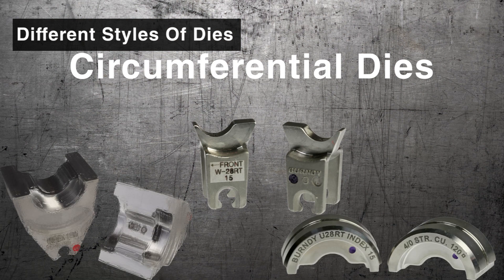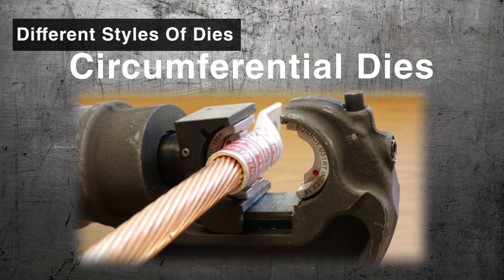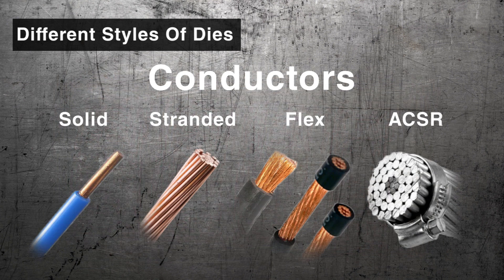Circumferential Dies produce circular indents on opposite sides of the compression barrel. Circumferential Dies are commonly used on solid, stranded, flex, and ACSR conductors, and are popular in construction and industrial applications and in overhead distribution.